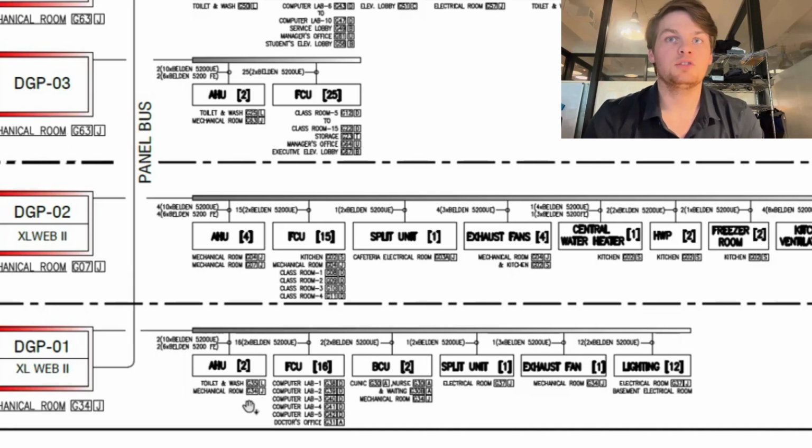Network and communication riser diagrams are especially useful for me because they show me on which networks I can discover specific devices that need to be programmed, as well as which JACE units serve which specific BACnet networks.